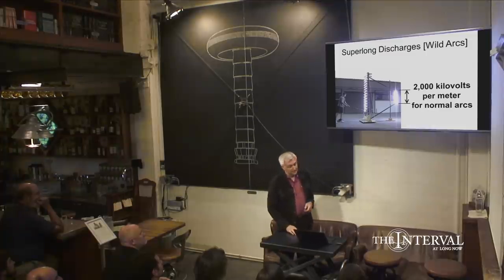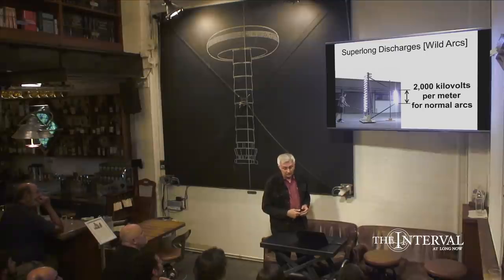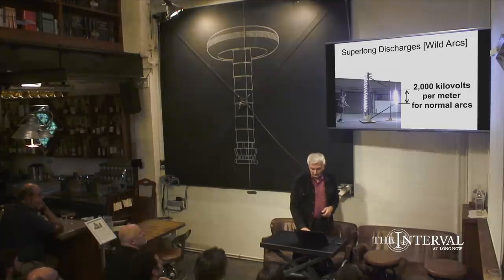The cost of breaking down air is well documented, and modern electrical insulators depend on this 2,000 kilovolts per meter value to successfully hold off voltages.